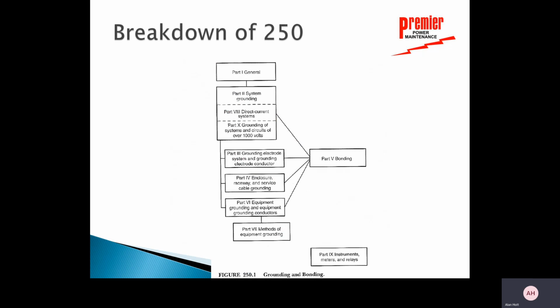So here's a breakdown of grounding and bonding. If we look at Article 250, there are several sections. We have the general section that we're going to talk about today. There's the system grounding section. Down here, there's a grounding electrode system that we get involved with quite a bit with fall of potential and point-to-point testing. Talks about raceway, grounding equipment and grounding conductors, methods of grounding electrical equipment.